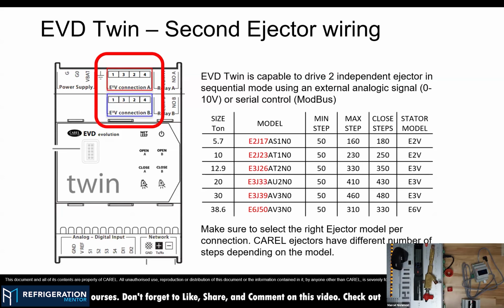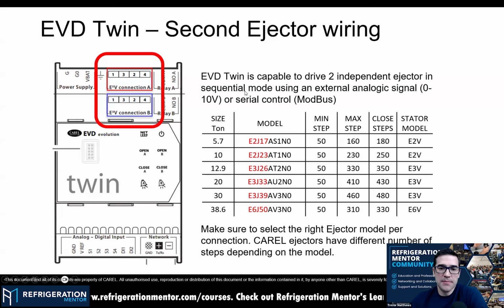Another important point, Trevor, is that different from our standard electronic expansion valves, ejectors have a different number of steps. So when selecting and installing or replacing the controller or the ejector in the field, make sure that you are selecting the right model that has the right amount of steps. Otherwise, you will not be opening completely or you would be overdriving the motor inside the ejector. Okay. Yeah, totally makes sense.